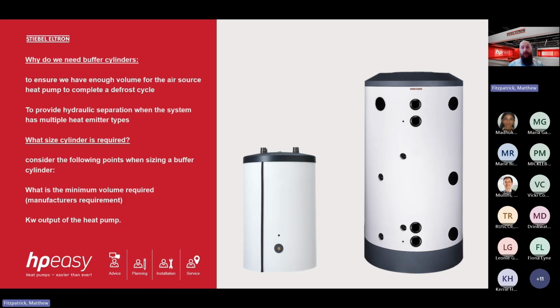So we look at buffer cylinder sizing. So we need to consider the following points. What's the minimum size required? Well, always look at the manufacturer's recommendations. They will know how much volume their product will need. For example, ours only require, probably say the most is 100 litres for a single system. If it's bufferless, it is slightly less. So the buffer cylinder is there and it's in line with the manufacturer's recommendations, which means there are no problems with warranty, servicing, repair, or the longevity or operation of the unit.